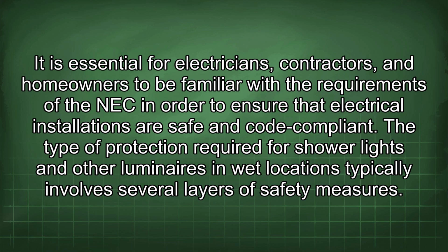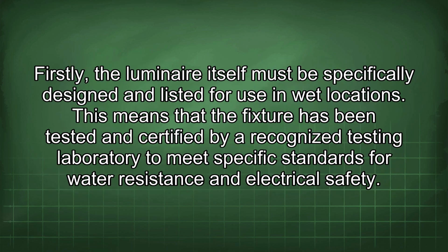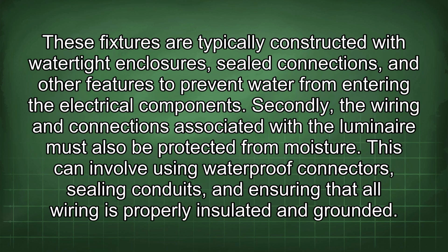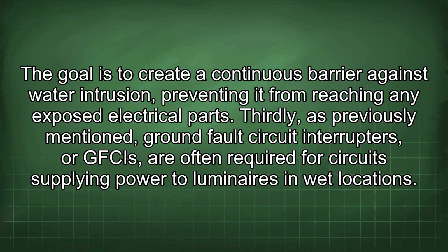The type of protection required for shower lights and other luminaires in wet locations typically involves several layers of safety measures. Firstly, the luminaire itself must be specifically designed and listed for use in wet locations. This means that the fixture has been tested and certified by a recognized testing laboratory to meet specific standards for water resistance and electrical safety. These fixtures are typically constructed with watertight enclosures, sealed connections, and other features to prevent water from entering the electrical components. Secondly, the wiring and connections associated with the luminaire must also be protected from moisture. This can involve using waterproof connectors, sealing conduits, and ensuring that all wiring is properly insulated and grounded. The goal is to create a continuous barrier against water intrusion, preventing it from reaching any exposed electrical parts.